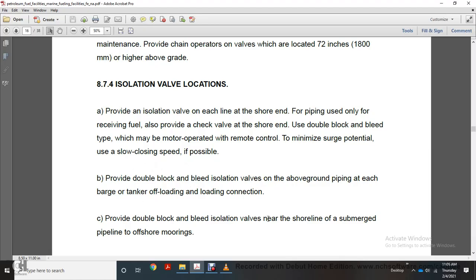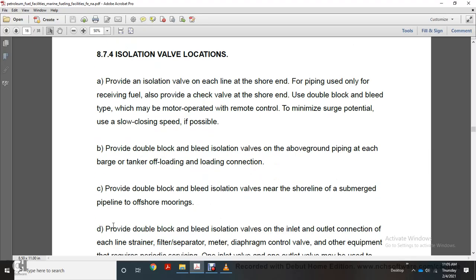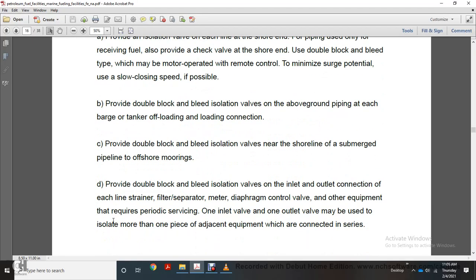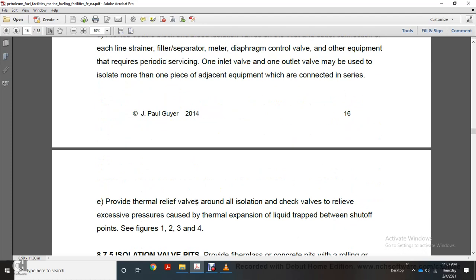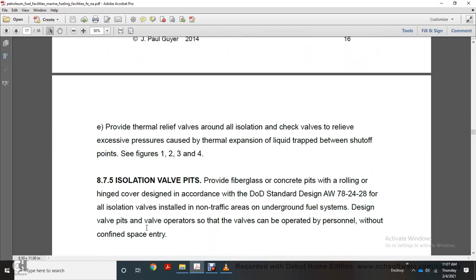Provide double block isolation valves near the shoreline on submerged pipeline offshore moorings. Provide double block and bleed isolation valves at the inlet and outlet connections of each line strainer, filter separator, meter, diaphragm control valve, and other equipment that requires periodic servicing. One inlet and one outlet valve may be used to isolate more than one piece of adjacent equipment connected in series. Provide a thermal relief valve around all isolation check valves to relieve the excessive pressure caused by thermal expansion of liquid trapped between shutoff points, figures 1, 2, 3, and 4.